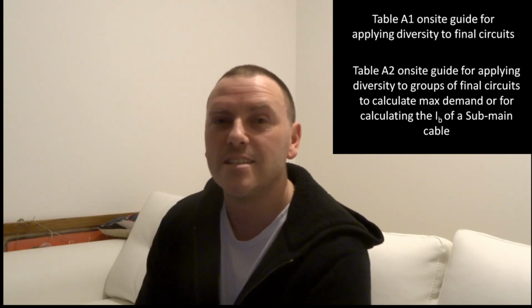Incidentally, we don't apply as much diversity to a shop. You'll notice on them tables that in a domestic environment for a lighting circuit we can use 66% of the full load, whereas in a commercial environment we have to use 90% of the full load. And that's down to the usage patterns. You go into a shop, you turn all the lights on, you leave them on all day, so they are on most of the time. Whereas at home, everybody's got different usage.